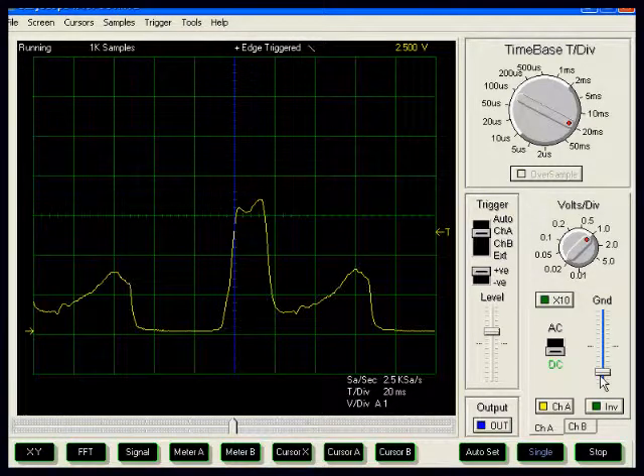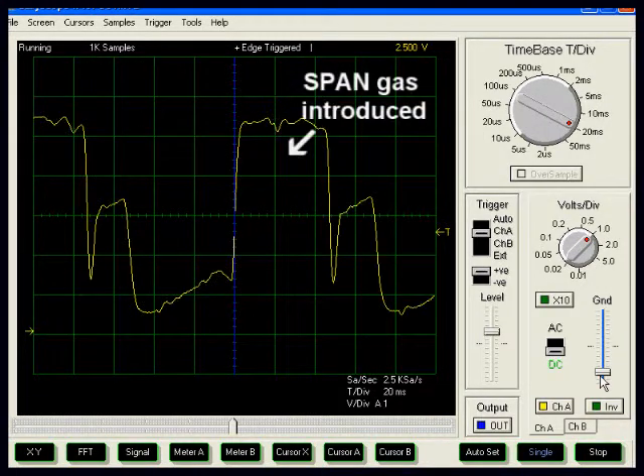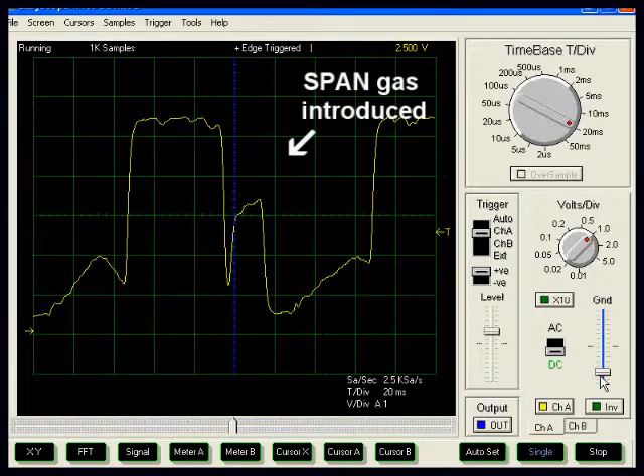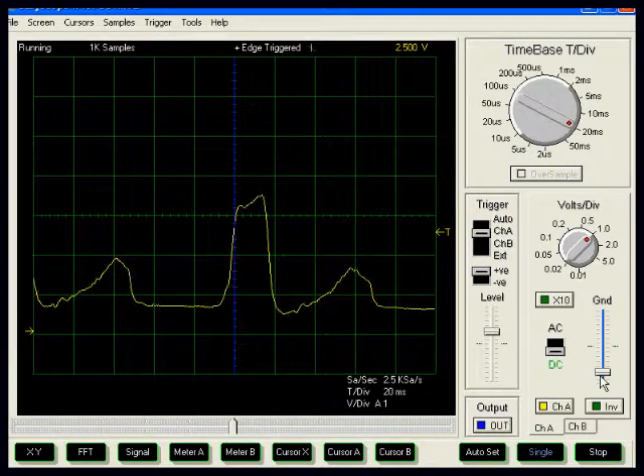If we introduce some span gas into the calibration system of our sample head, we can actually backflow this calibration gas, and this will rise up to show 50,000 parts per million. This will occur just at the invalid parts of the cycle.